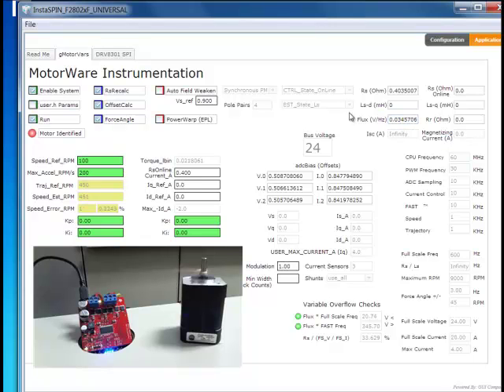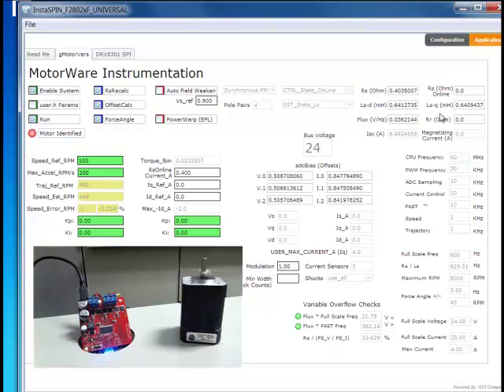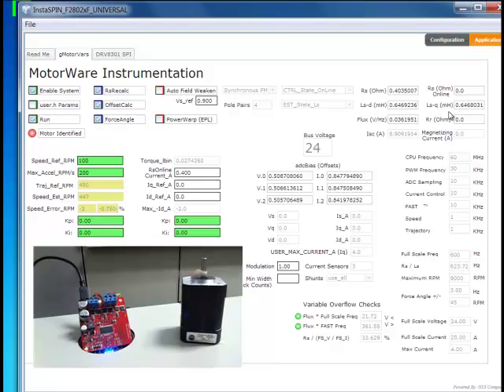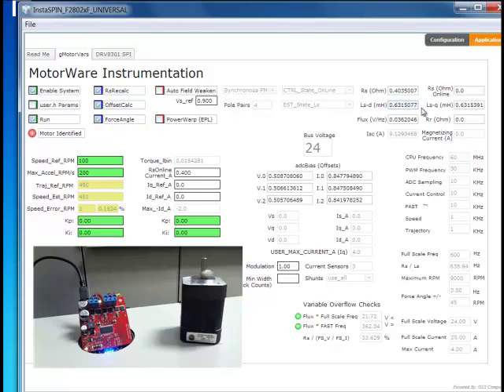And you can see that we're looking at the flux and have narrowed in on the rate of flux. We've now moved into the inductance phase. So we're now actually injecting a little bit of negative ID current, field weakening, and using that for the inductance test. And you can see that we're zeroing in on that inductance as well.